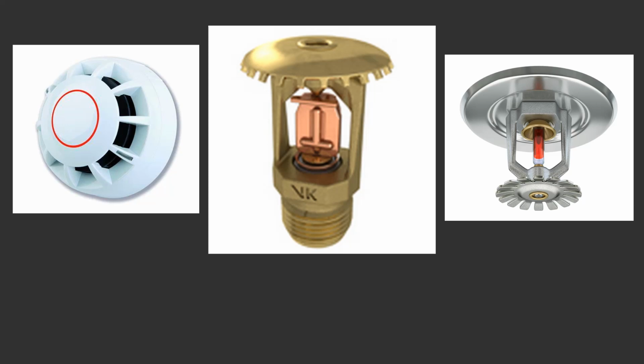More you know. This guy in the middle is our fusible link. It's a little metal thing in the sprinkler head that holds it shut. That little copper-colored metal device is designed in such a way that it melts at a specific temperature. So let's say 180 degrees, keep it simple. At 180 degrees, that melts and lets it out of the way, and then the little spring plunger can open and water comes out of the sprinkler head.